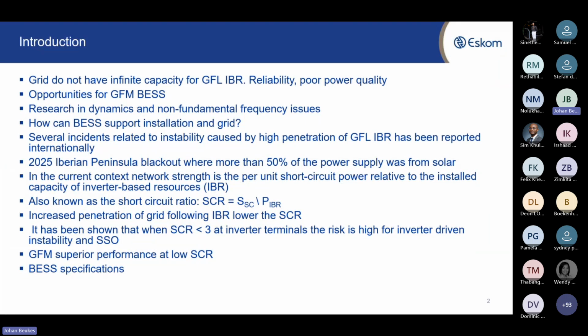And what happened there is that, the first reason why it happened is that at that stage a significant portion of the generation was IBR based. And the second thing that's important to realize is that they were not aware, they didn't look at the signals, and they couldn't predict it before it happened. And it was a cascading effect, and that will also become clear. So there's two things. We need to understand what is happening on the grid. And the second thing is we need to know what to look at. And we must make sure that the power quality parameters that we're looking at are the right parameters. Do we measure the right stuff?